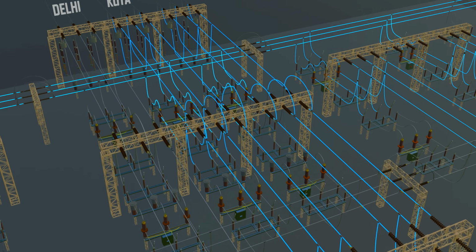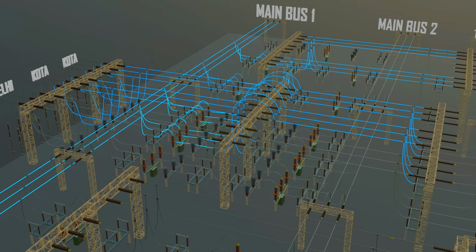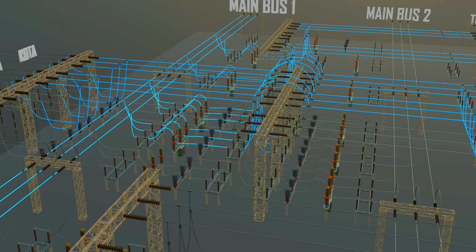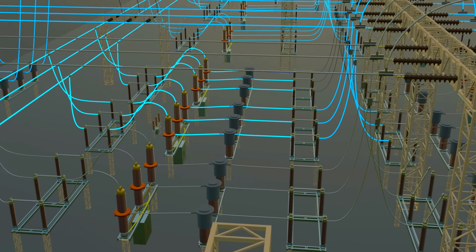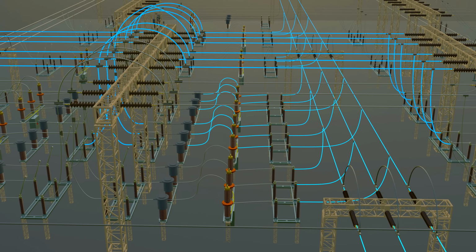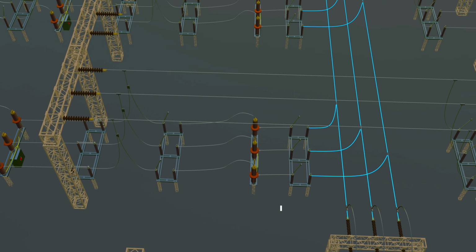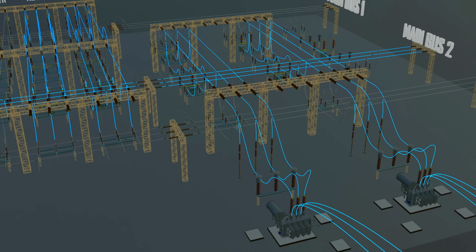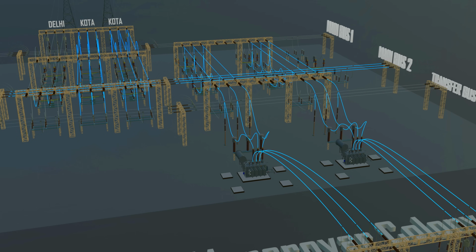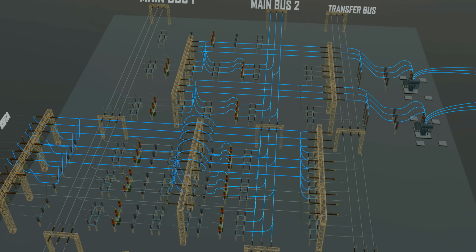Now suppose a component connected to main bus 1 develops a fault or needs scheduled maintenance. In such cases, the isolators and circuit breakers of main bus 1 are opened, and the load is shifted to main bus 2 to maintain uninterrupted power flow. On the load side of main bus 2, the supply flows through an isolator, circuit breaker, isolator sequence, then rises through the gantry tower to energize the connected transformer.